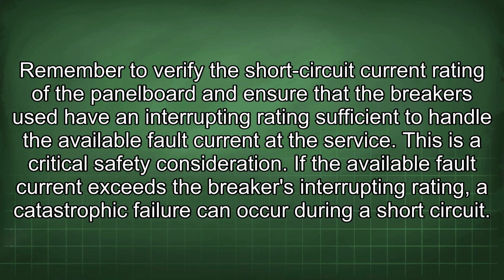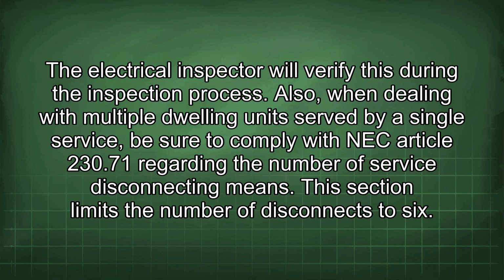This is a critical safety consideration. If the available fault current exceeds the breaker's interrupting rating, a catastrophic failure can occur during a short circuit. The electrical inspector will verify this during the inspection process.